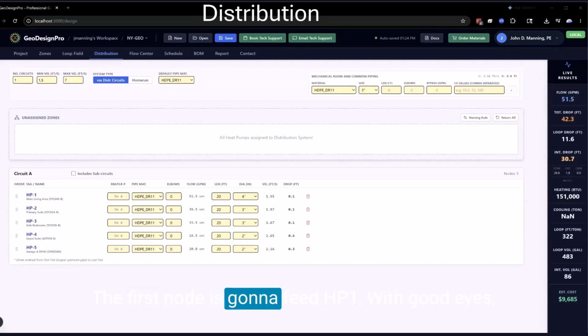The first node is going to feed HP1. With good eyes, you can see that it puts the name of the zone and the heat pump size in the description on the left. You're modeling what's upstream of that T that's feeding the heat pump. The program will automatically pick a diameter based on keeping the velocity above 1.5 feet per second. It'll tell you the pressure drop in that upstream pipe. If for any reason they aren't fed in this order, you can simply drag and drop them in a different order and it will recalculate everything.